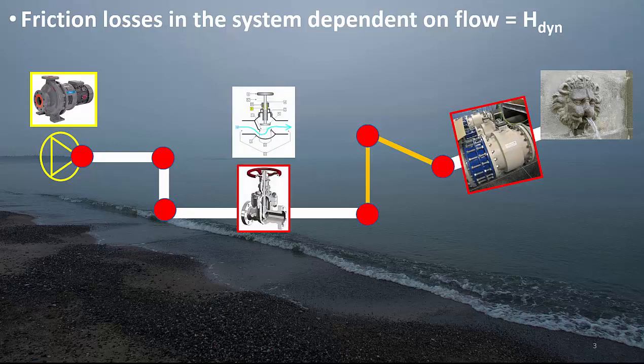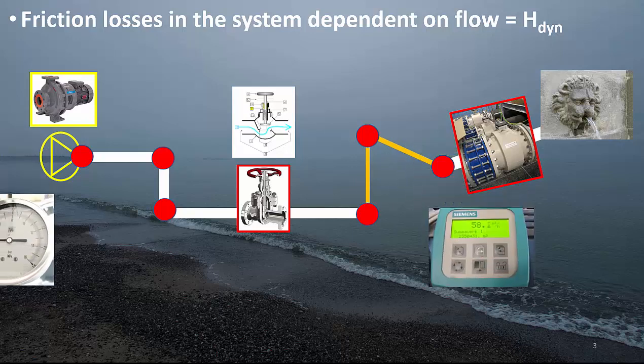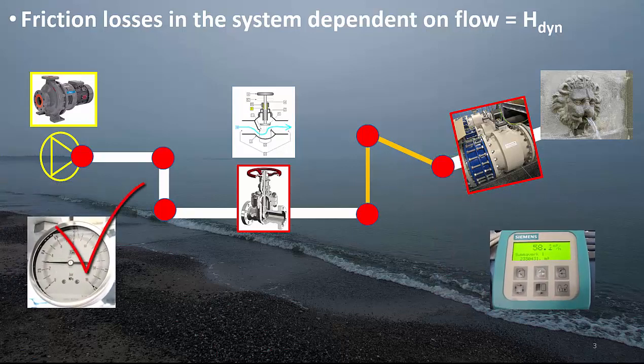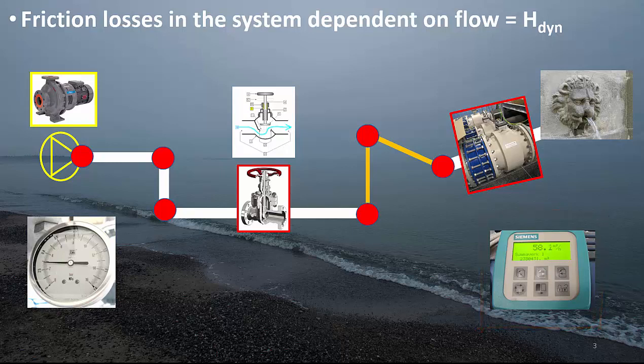But there is more. You have valves, you have flow meters, you can even have static mixers where you want to mix in a chemical, mounted inside or on the pipe, that will create pressure losses when the water goes through them. When you have looked at the whole system — the piping, the diameters, the pipe length, how it turns, what type of valves are installed, flow meters, etc. — then you can calculate the pressure losses in the whole piping system. That pressure, illustrated here by a manual pressure gauge, is the pressure that the pump needs to pump at that flow, illustrated here with a picture of a flow meter, to get the water to the lion head outlet.